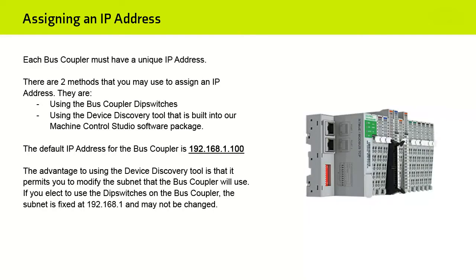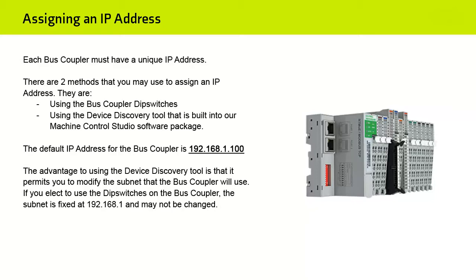Each Bus Coupler must have a unique IP address. There are two methods that you may use to assign an IP address. They are using the Bus Coupler DIP switches or using the Device Discovery Tool that's built into our Machine Control Studio software package. The default IP address for the Bus Coupler is 192.168.1.100.